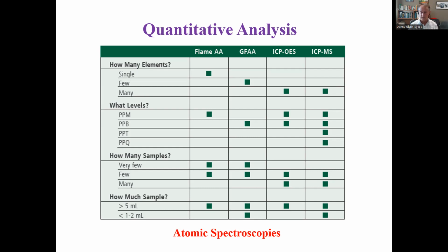spectroscopies that are used for the analysis of lead, there's flame AA, which is very common. It's not an expensive instrument, so many labs have them, but it has some drawbacks, which we'll explain a little bit later. And in this case, if you're looking for a metal like lead below the part per million level, flame AA can't see it. So it is sensitive to lead. You can optimize for the analysis of lead, but if the lead concentration dips below about 1 ppm, the instrument's going to say it's not there.